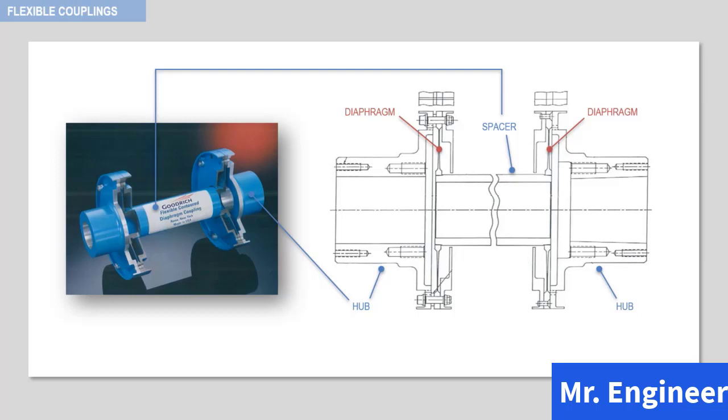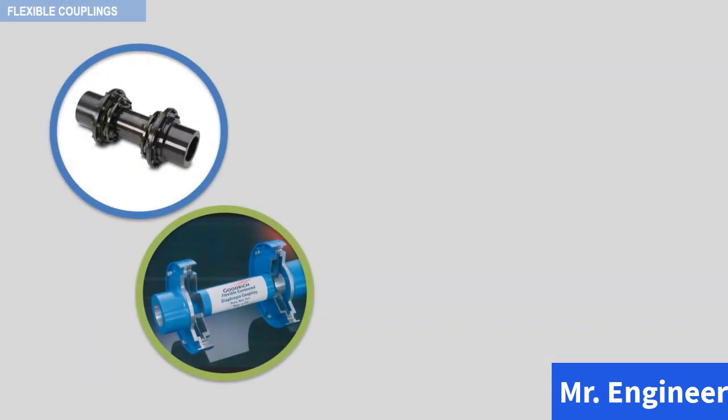Regardless of the type of diaphragm coupling, it is common practice to pre-stretch these couplings to take full advantage of the maximum available end float. Always remember to ask equipment vendors to provide axial shaft movement calculations in order to confirm that the coupling maximum end float is not exceeded.